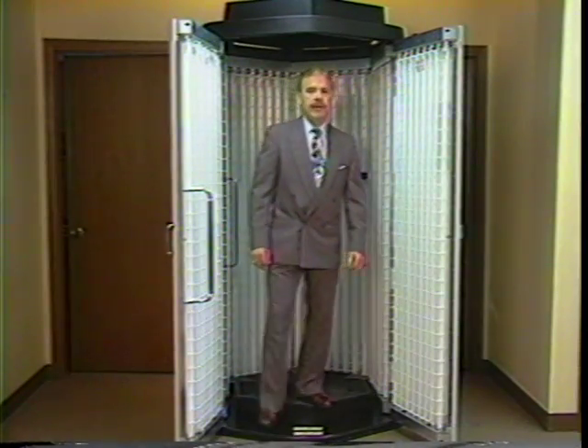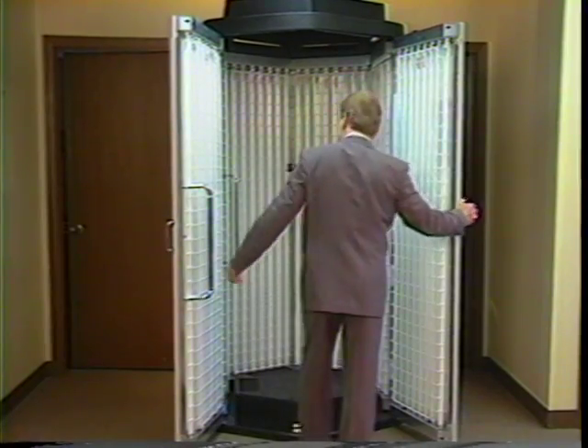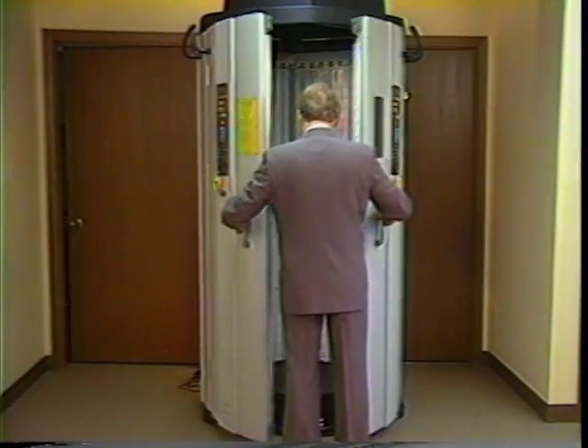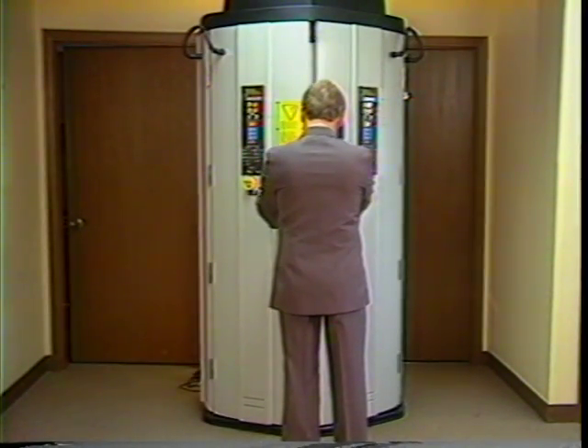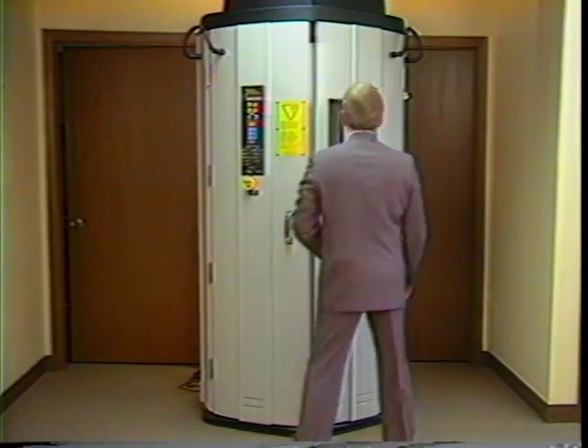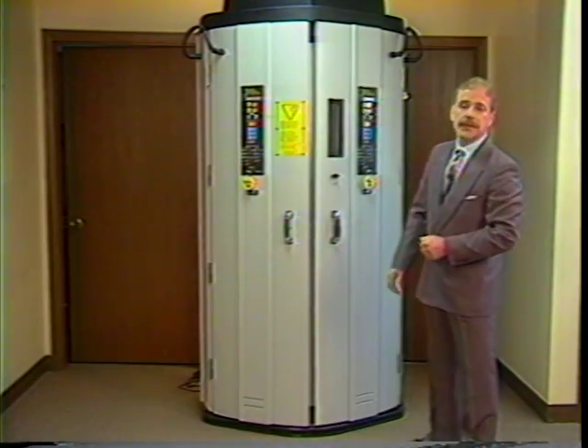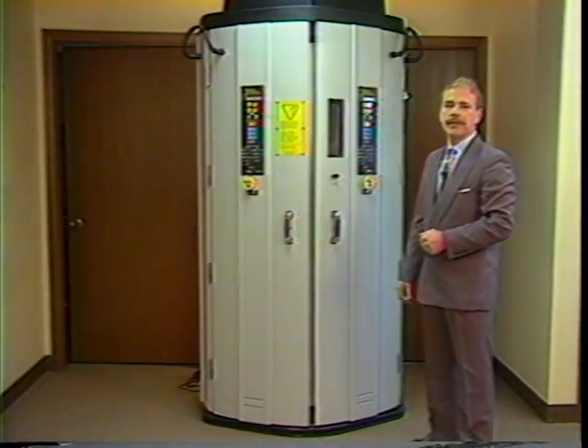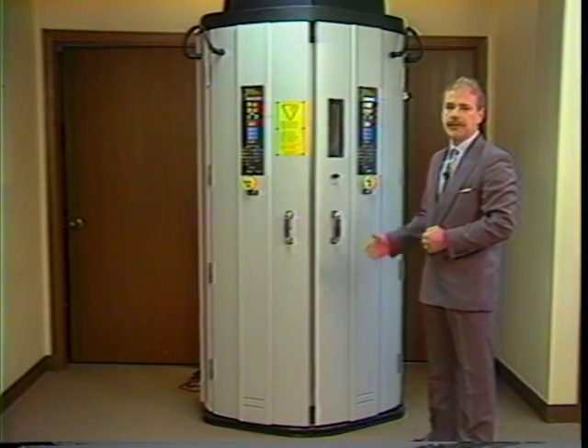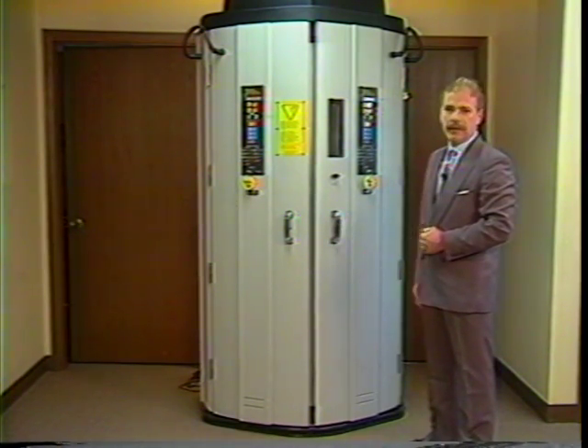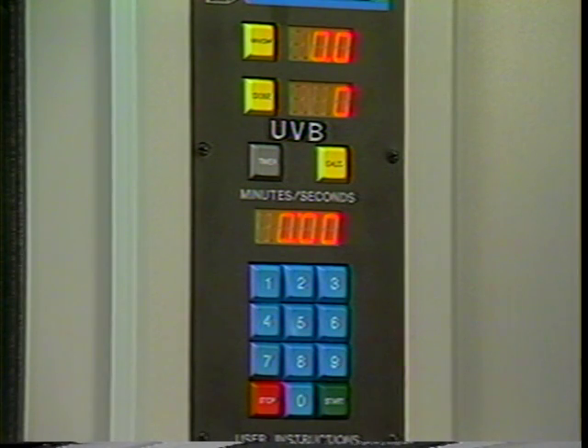A warm-up period of 5 minutes is necessary to allow the lamps to reach their normal operating temperature. This is also necessary for an accurate meter reading. This is normally done immediately before the first treatment of the day. First, you close the doors as I've shown you, and on the UVB timer, with the key turned to the lamp's on position, depress the gray button marked timer.